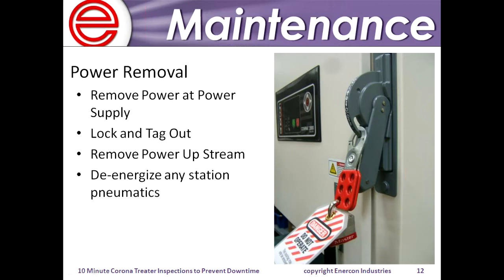In addition, speaking specifically to the Corona treater: make sure the breaker on our power supply controller is shut off and locked out. Also remove any power upstream — there should be a disconnect box upstream of the power supply, and make sure that's shut off too. Also de-energize any station pneumatics. Before doing any work, shut off the ball valve for the compressed air, then bleed off the compressed air lines so there's no stored potential.